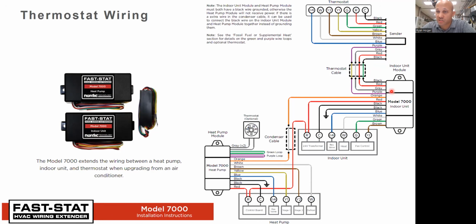And then this box's job is to separate them from 4 back into 7 again. So the thermostat thinks he's got 7 things connected. The indoor air handler thinks he's got 7 things connected, but really in the wall, there's only 4 wires run. And these 2 boxes are basically the sender box sends a little email to the indoor unit boxes. Hey, dude, I'd actually like second stage of cooling, please. Like, could you hook me up? And that guy's job is to then go ahead and turn that relay on. So the indoor air handler thinks this box is his thermostat. He has no idea it's not his thermostat. And the thermostat thinks this box is his indoor air handler. He has no idea that it's not.